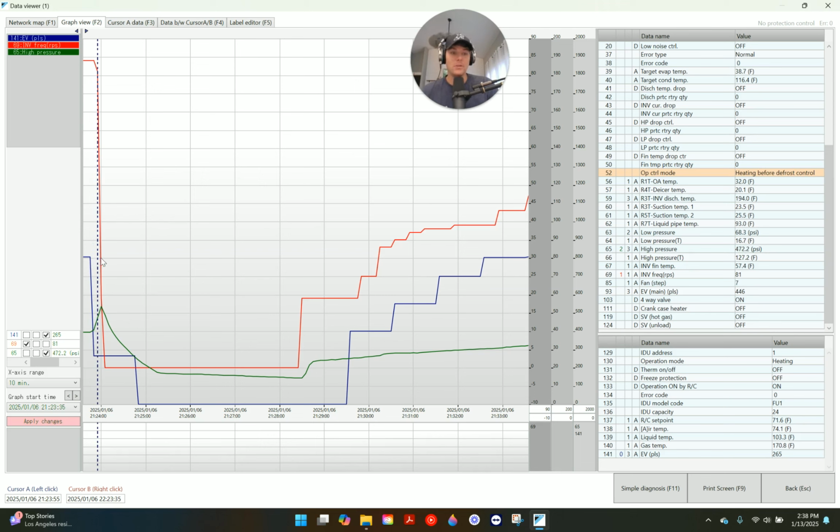And then we jump in a little bit further here, and then, whoa, okay, we've got a problem. My head pressure is 534 PSI, right? See that green spike here on my screen right here? That is my head pressure.